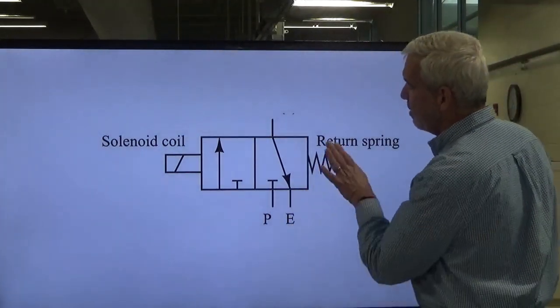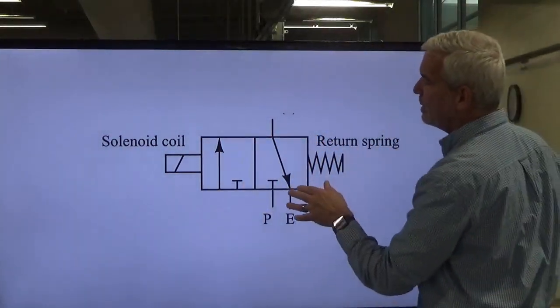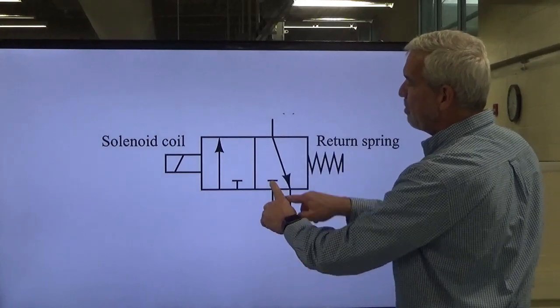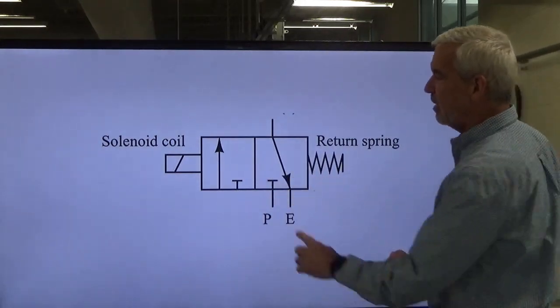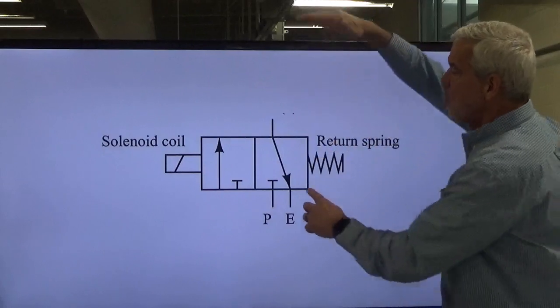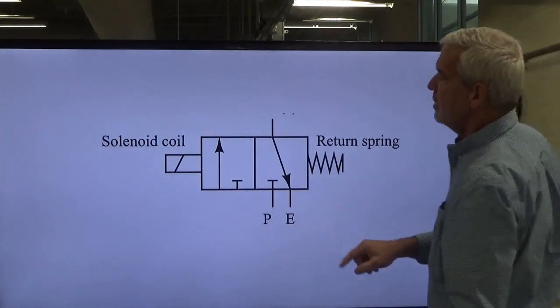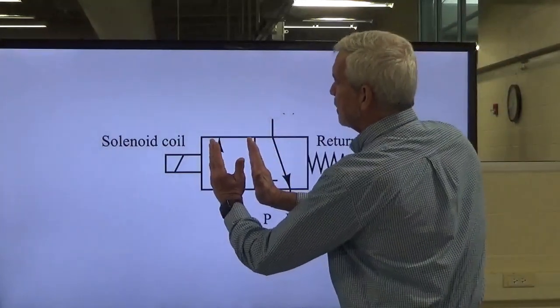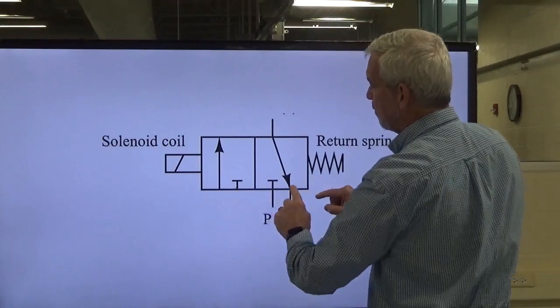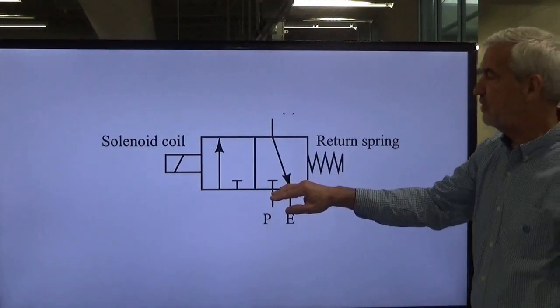These arrows mean pathways. This symbol is a spring, and the arrow through it tells us it's variable. You've got a solenoid on one side to move the valve body and a return spring to push it back. In this case we're de-energized, spring pressure is dominant. We're not allowing system pressure from our regulator to go anywhere - it's blocked. However, downstream pressure has a pathway to exhaust to atmosphere.